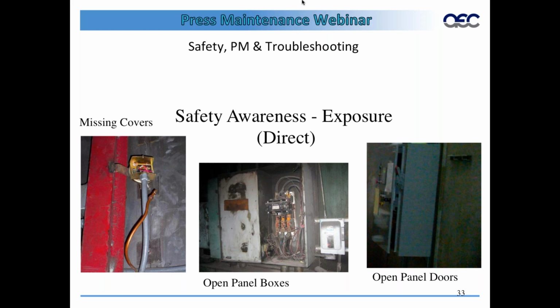So here, the one picture is a case of a switch that somebody probably had to check. Whatever they had to do to it, they left the cover off, thinking, well, okay, it'll still work. However, this leaves the exposure for somebody to either touch it or some other element to get in there and short it out, or even just the atmosphere. The middle one looks pretty bad as well. It's wide open. You can see it's three-phase, so more than likely it's 240, 480, or even higher. And it's just waiting there for something to get in it and be a major situation.